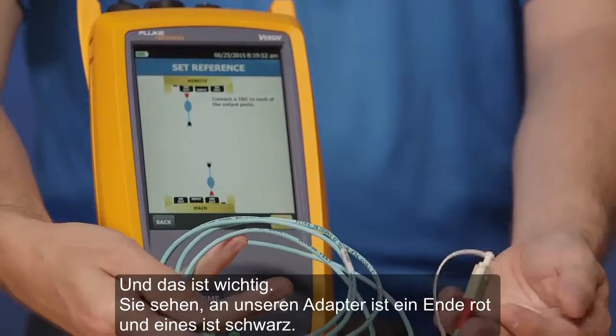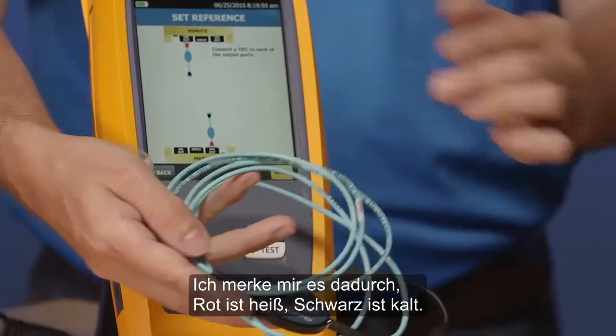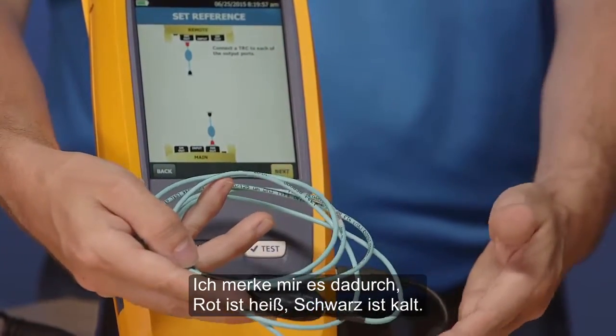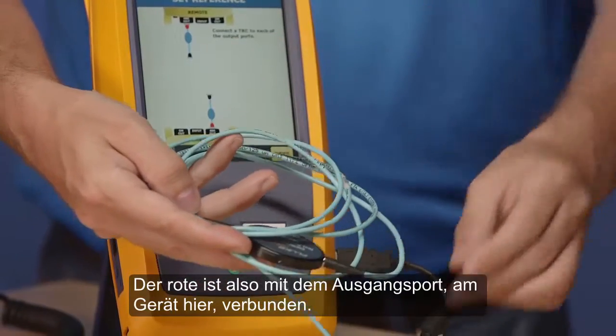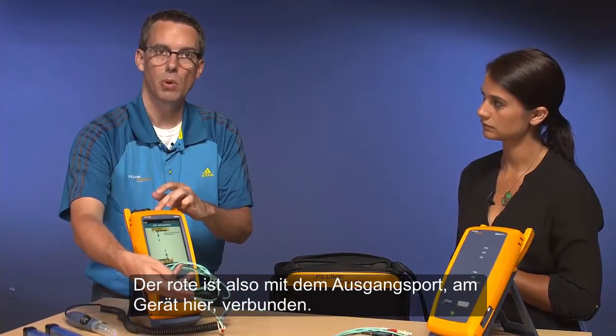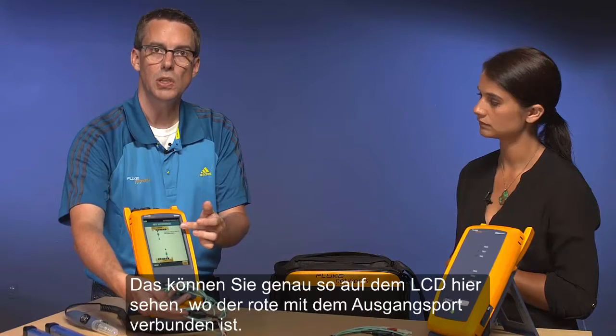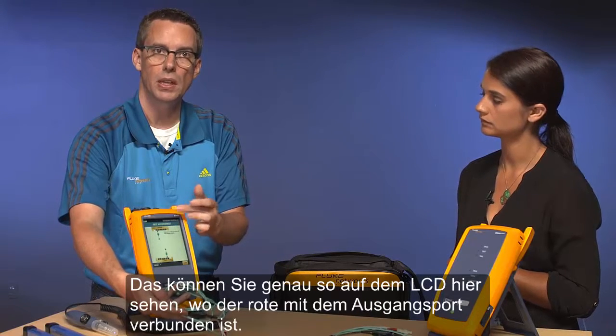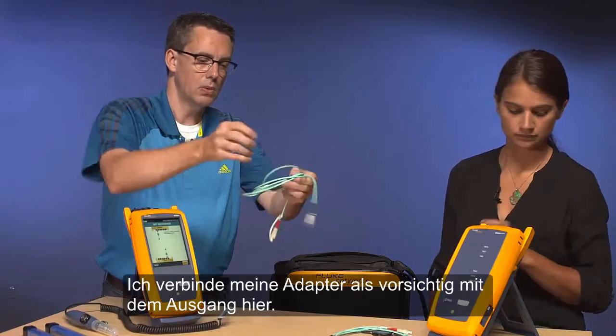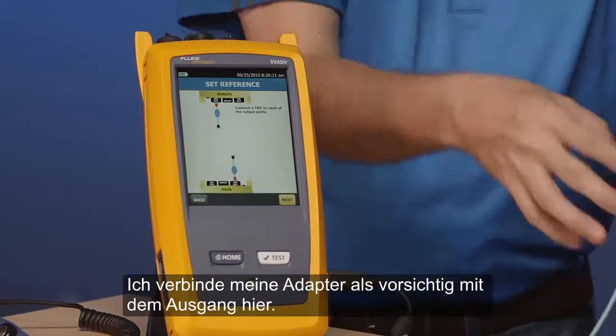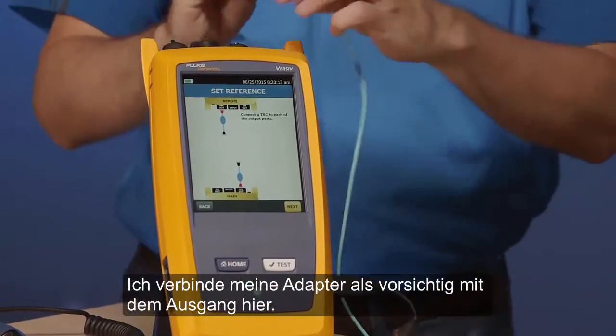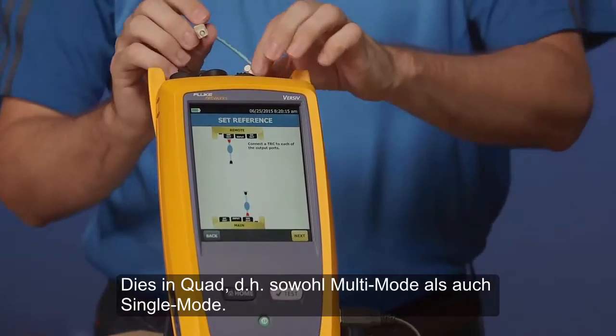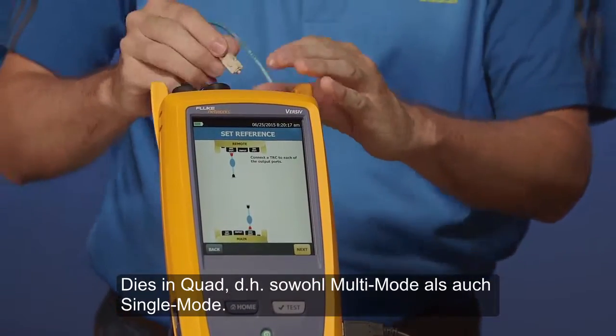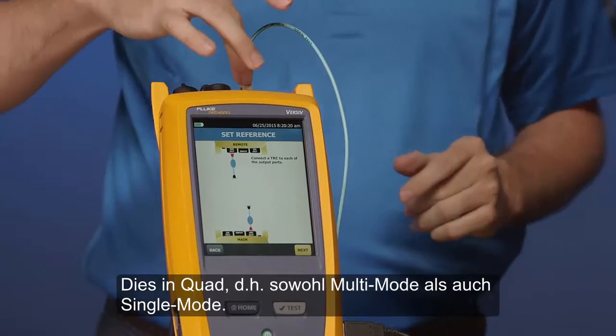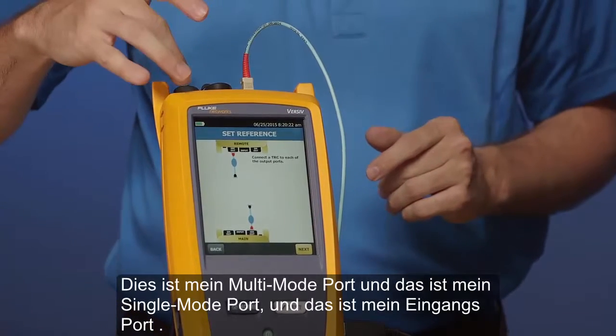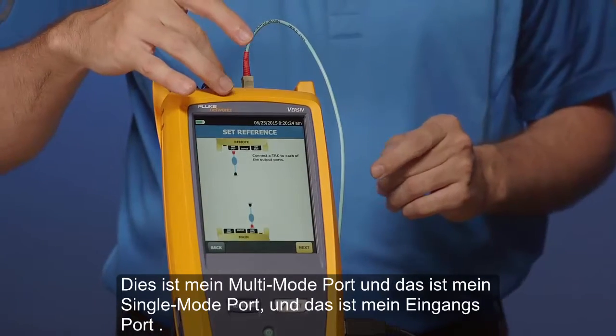You'll notice on our cords that one end is red, the other is black. The way that I like to remember this is red is hot, black is cold. So the red is connected to the output port on the instrument here, but you can also see that on the LCD here where the red is connected to the output port. So I'm going to gently connect my cords to the output port here. And this is a quad, which means it's both multi-mode and single mode. So this is my multi-mode port, and this is my single mode port, and this is my input port.